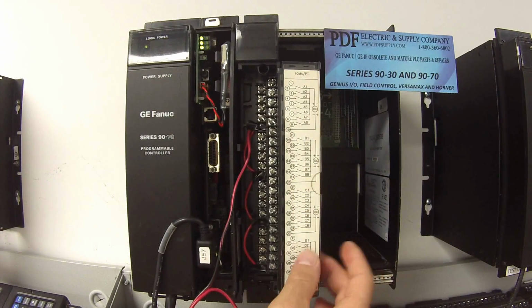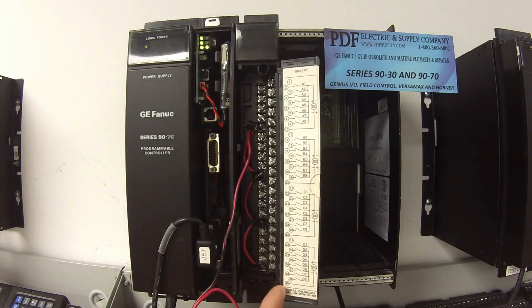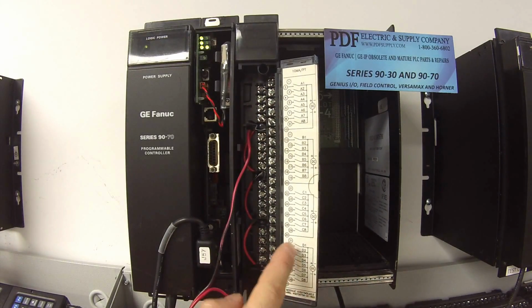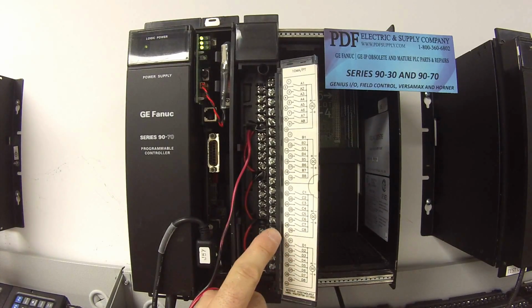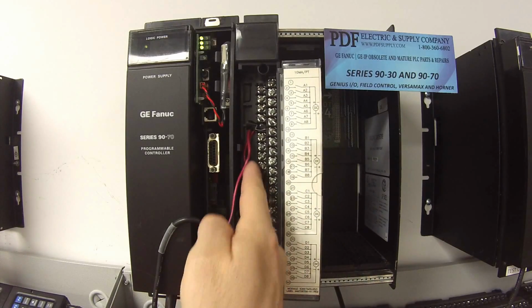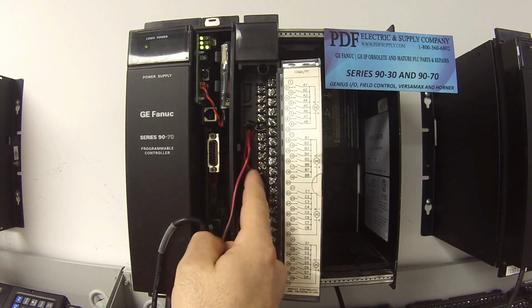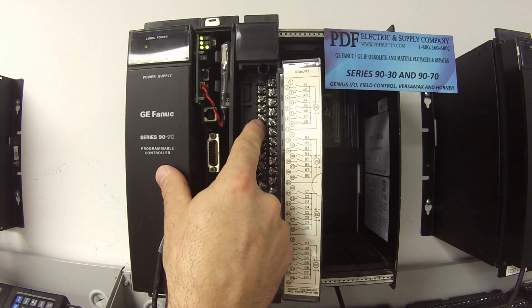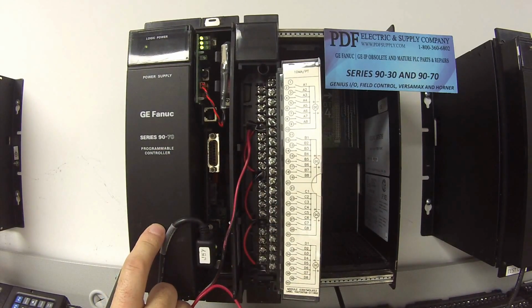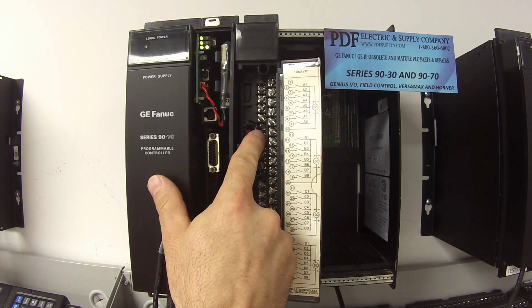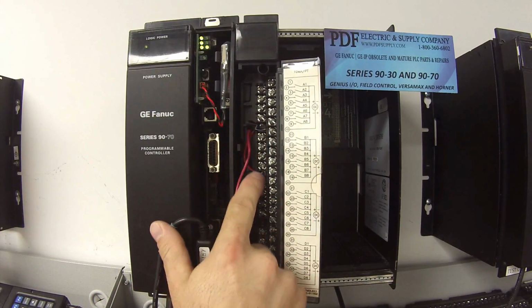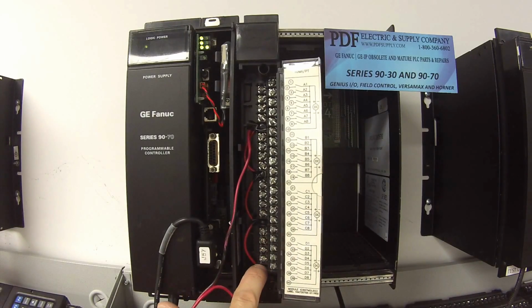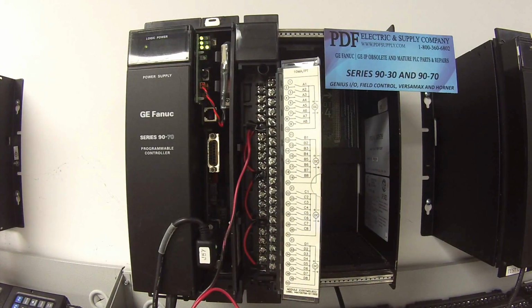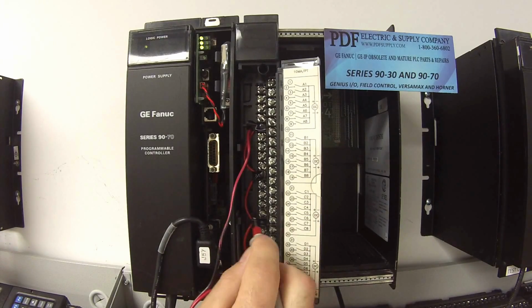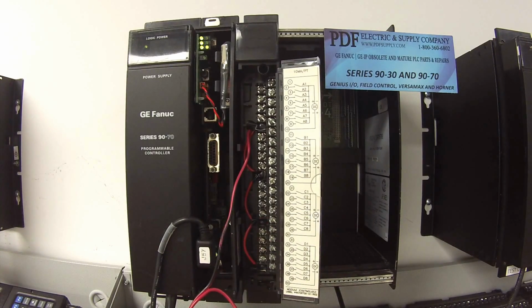One note I wanted to touch on again: pay attention to the door card and where it's asking you to probe the terminals or connect to them, and where it's asking you to put your positive and negative permanent lead. I have this pre-jumpered for this test on 10, 20, 30, and 40, again using my negative lead from a 24-volt DC power supply. And you'll note I've taken the liberty of putting a small piece of electrical tape over each of the terminals 10, 20, 30, and 40.